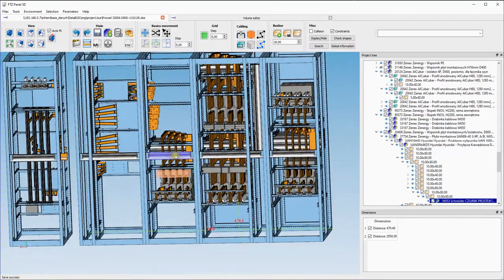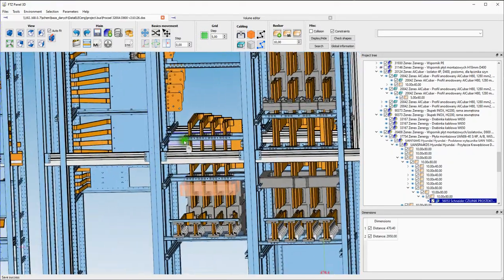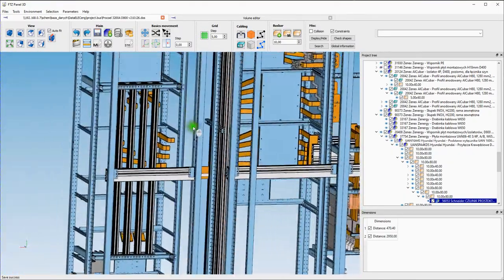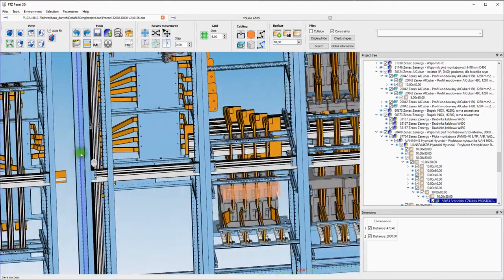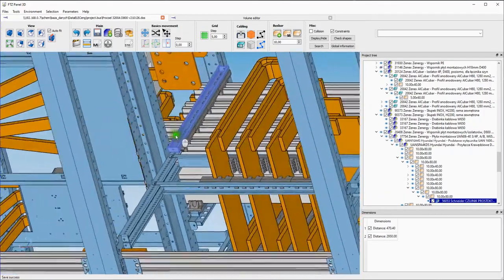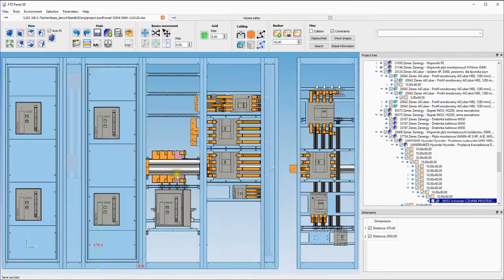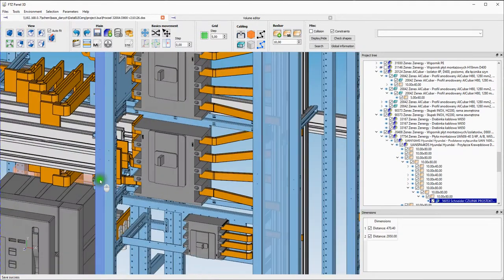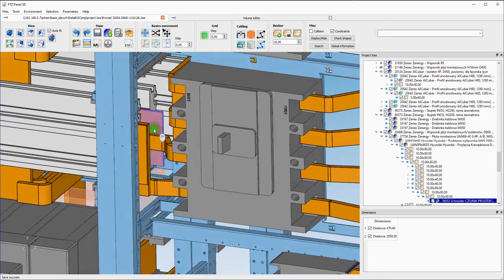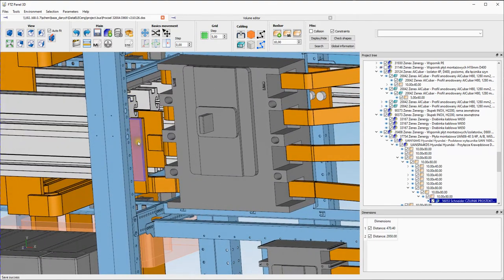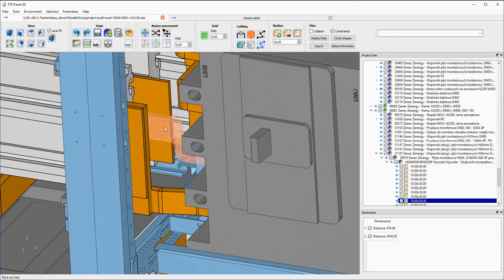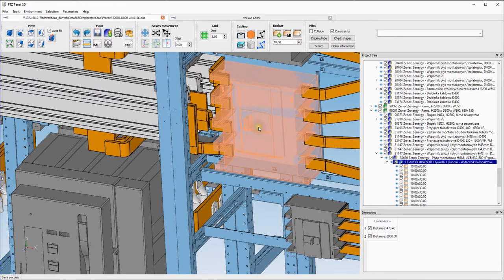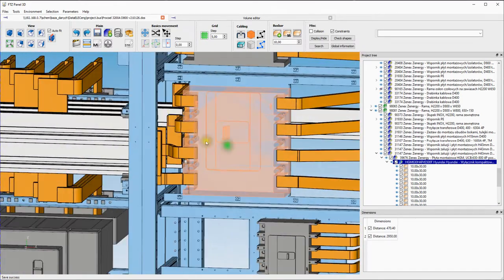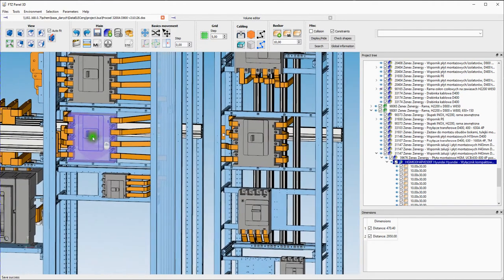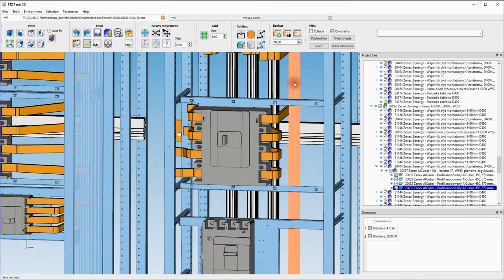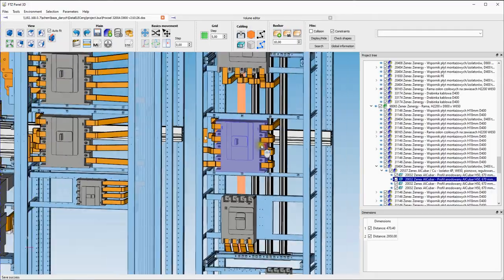Normally, yesterday, for further outgoings, the option was like this. I put it separately here. From the main duct, let's say, I show it from the front. From the main 3200 ampere duct, it supplies this 500 ampere breaker, which is on the schema. So it supplies, and the old option was that the bus bars were going to the back, behind the breaker.